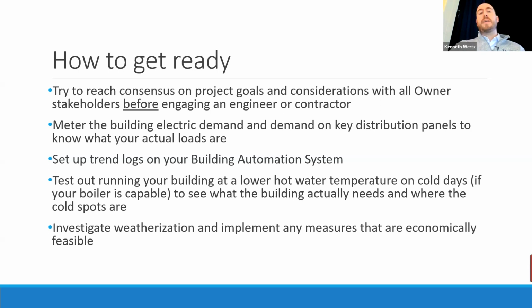For a lot of these projects, in order to know how much you would need to increase the service, or if you need to increase the service, you need to have hard data around how much electricity you're actually using right now. And that's more than just looking at your monthly bills. In some cases, if you have a bigger building, the utility's measuring how much electricity you're using every 15 minutes, but that's not every building. And if you're not one of those, I would definitely advise working with an electrician and trying to get some meters installed, temporarily for like a month or so to get a sense of how much power you're actually drawing.